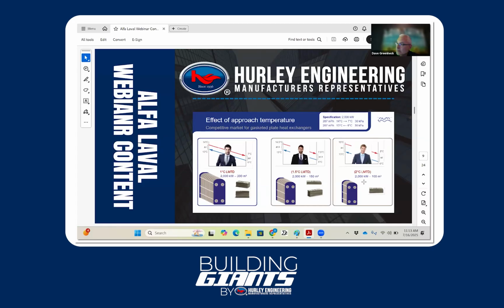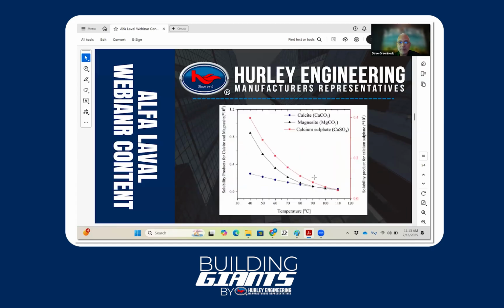There is a diminishing return you'll get in heat exchangers, same with towers and other devices, coils and chillers, where you don't get the juice for the squeeze if you keep adding surface area. In gasket plate and brazed plate heat exchangers, there are other consequences that result from too much surface.